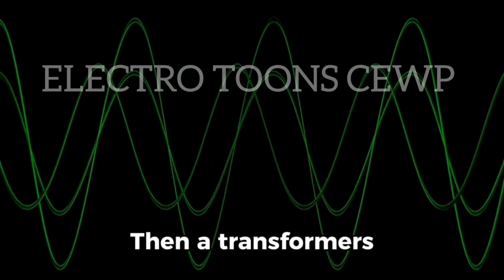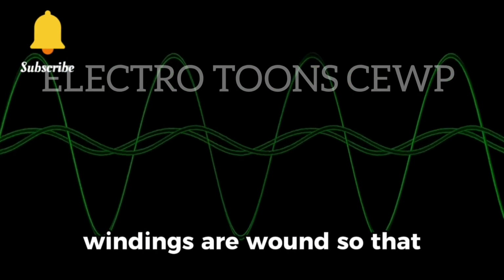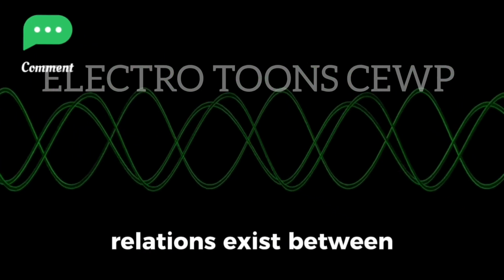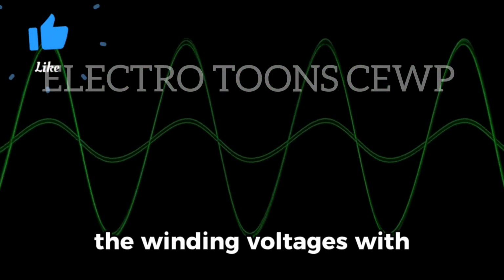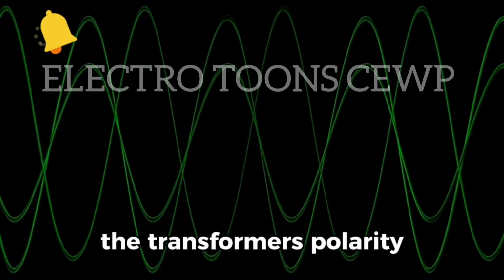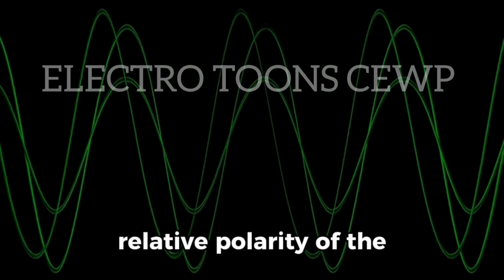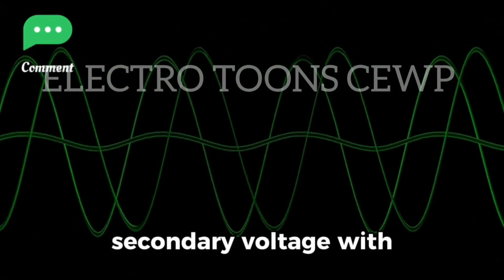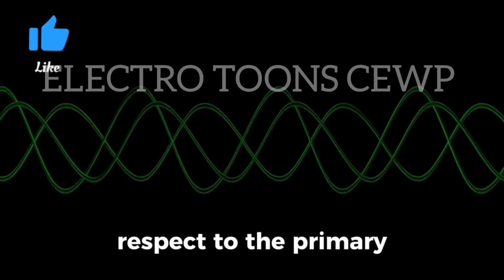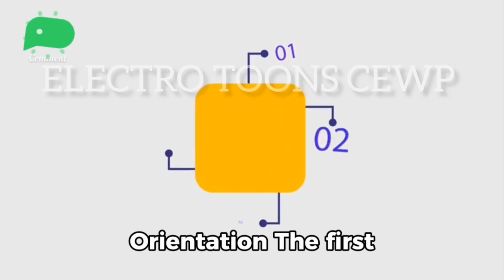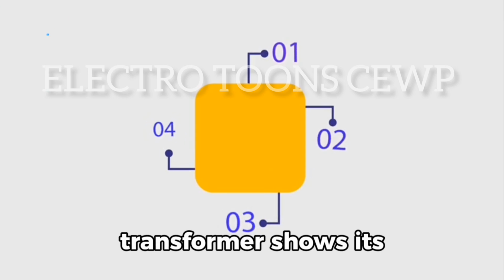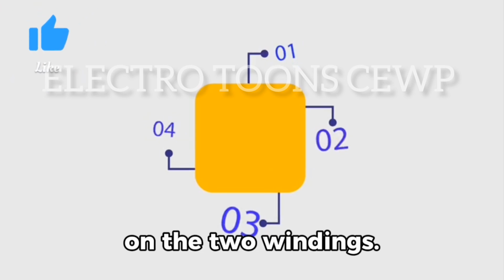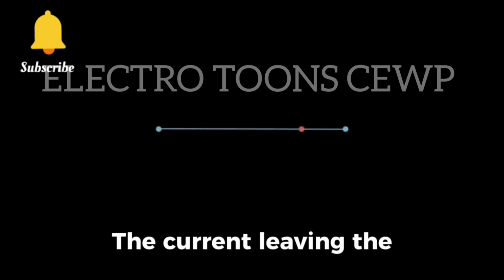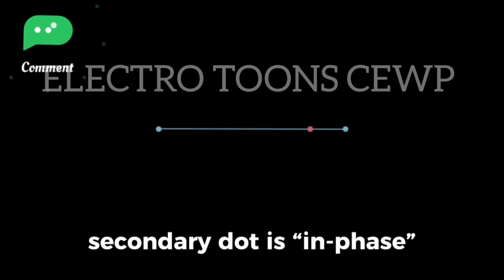Then a transformer's windings are wound so that the correct phase relations exist between the winding voltages, with the transformer's polarity being defined as the relative polarity of the secondary voltage with respect to the primary voltage as shown below. Transformer dot orientation. The first transformer shows its two dots side by side on the two windings. The current leaving the secondary dot is in phase with the current entering the primary side dot.